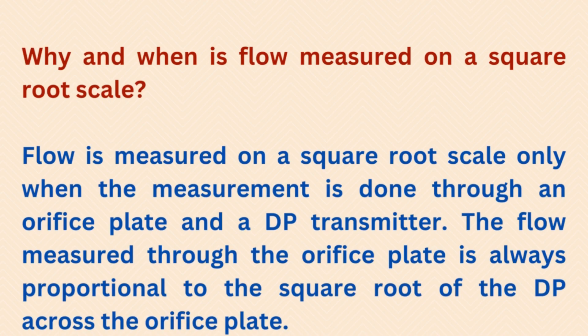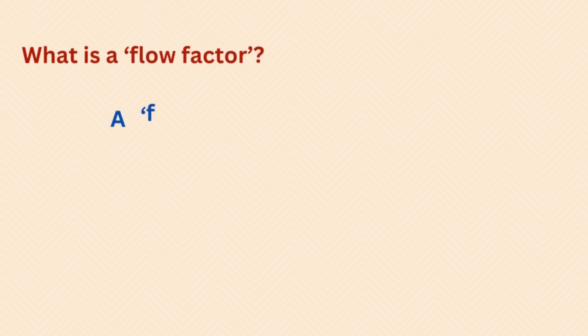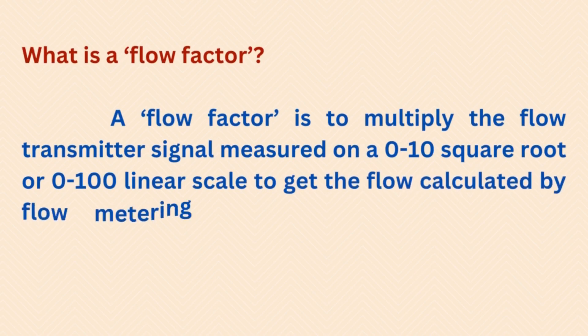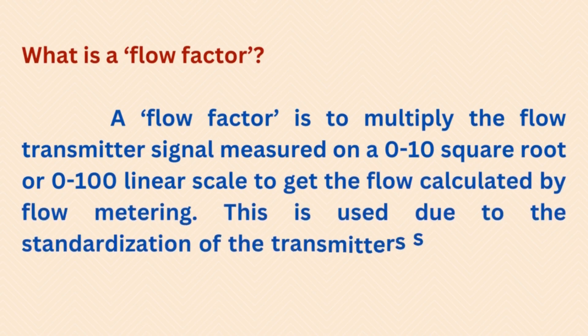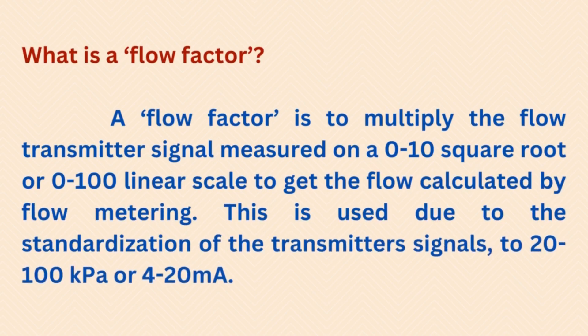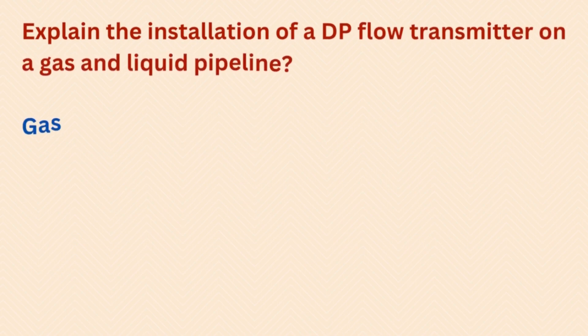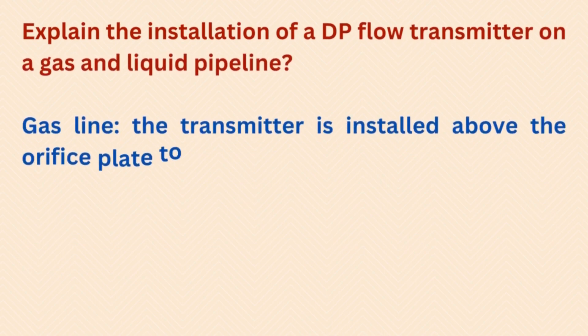What is a flow factor? A flow factor is used to multiply the flow transmitter signal, measured on a 0 to 10 square root or 0 to 100 linear scale, to get the flow calculated by flow metering. This is used due to the standardization of transmitter signals to 20 to 100 kilopascal or 4 to 20 milliampere.